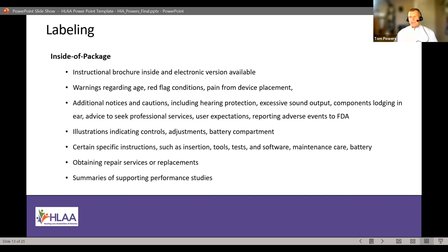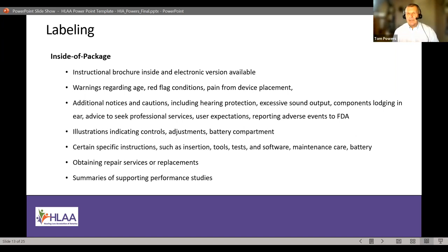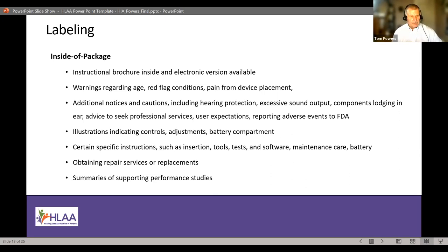There should be illustrations and diagrams of the controls, the battery compartment, and how all those things work — along with instructions on the tools, software, maintenance, how to change or recharge the battery, how to get repairs, and how to get replacements if the device becomes defective under warranty. Particularly for the self-fit category, the manufacturer must submit to the FDA clinical data showing the efficacy of the self-fitting procedure — that it can actually be done by individuals and results in a reasonable fit for a particular audiogram.